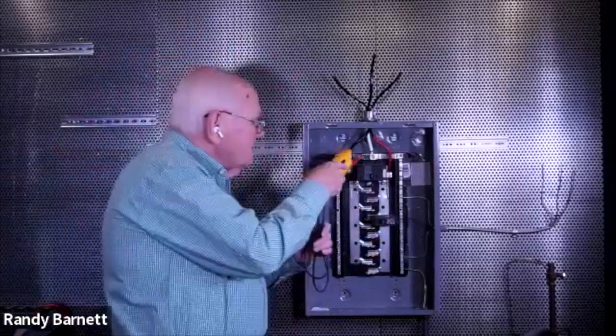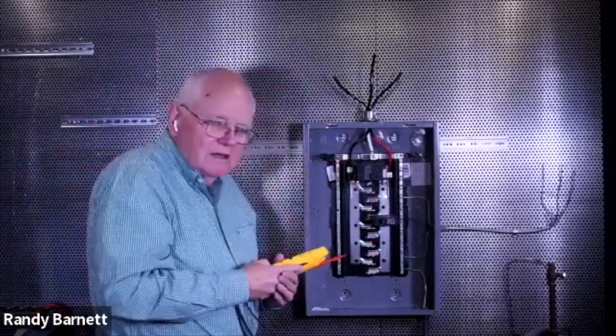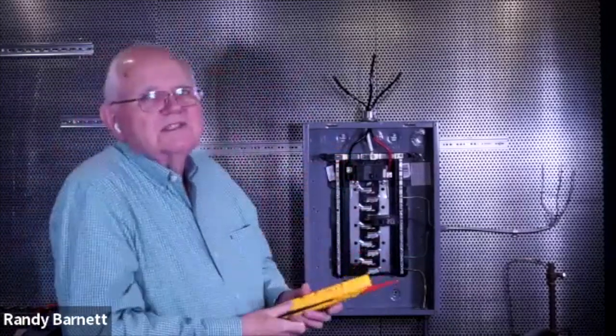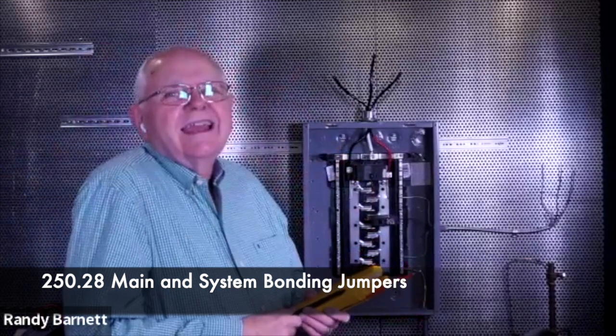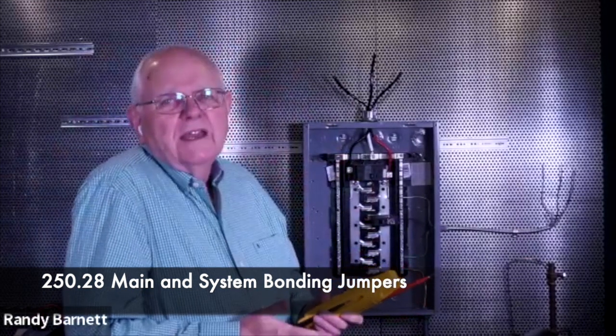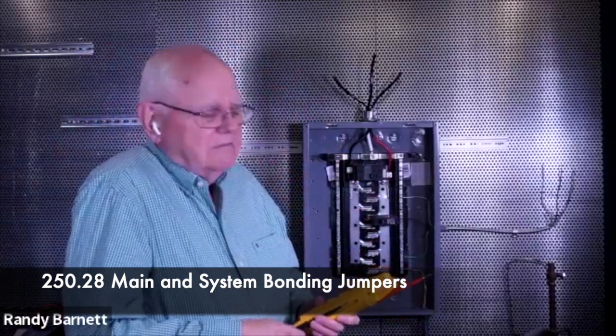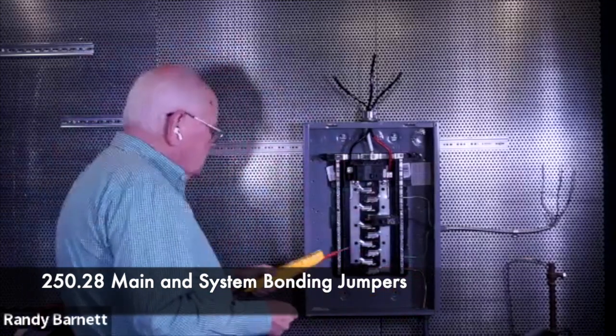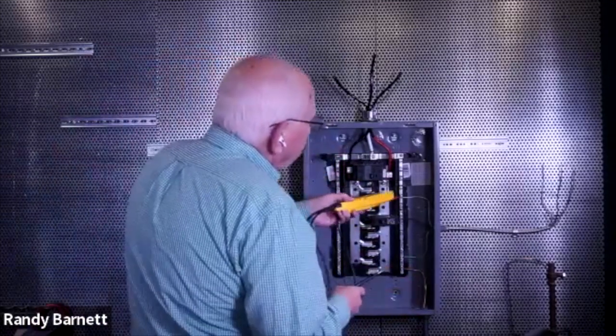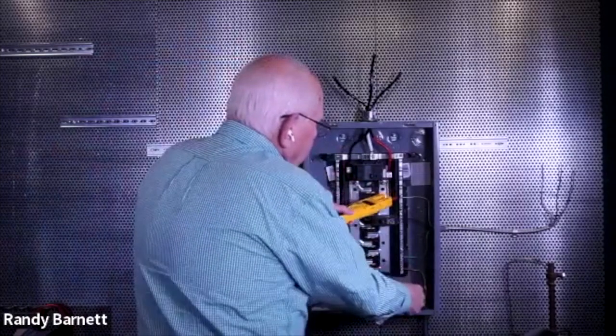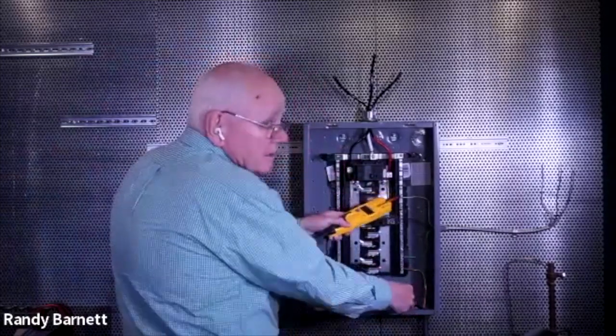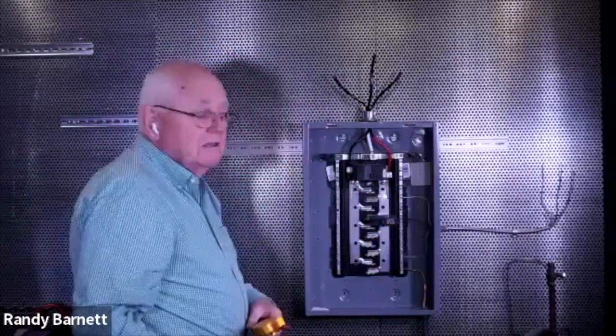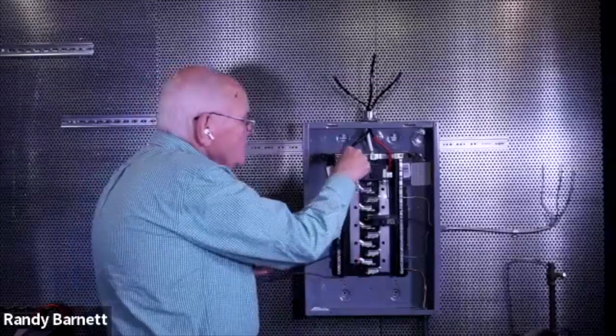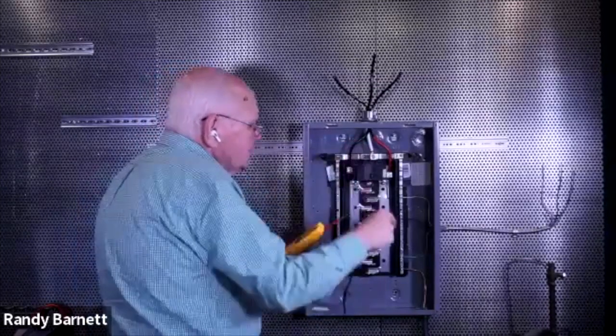Right now, the main bonding jumper is screwed in. When we buy the panel, it's already sized. 250.28 has all the requirements for the main and system bonding jumpers in it. So right now, if I were to try to read resistance between this bus bar, the grounded bus bar, and the metal frame of the equipment, my meter beeps. I get 0 ohms. Why? Because that green screw is screwed in, connected to the cabinet.